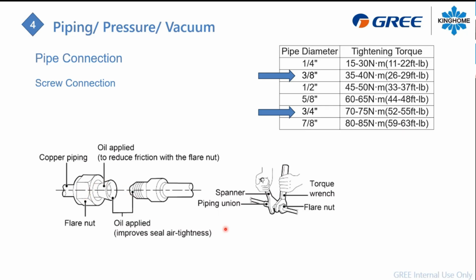from your flare connection. Because sometimes an installation looks very great, everything is in line, everything is tight, you have a lot attached to the wall and nothing's moving, but then when the piping tries to naturally move because of the expansion and contraction of the copper, well, the weak point is your flare connection. So it can cause a leak in a year, 2 years, 3 years, even if your flare is perfect. It's natural, the copper will move. So make sure you have enough flexibility in your piping line to avoid that kind of leak in a couple of years.